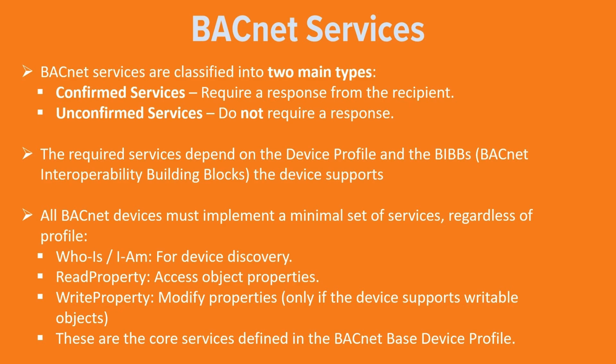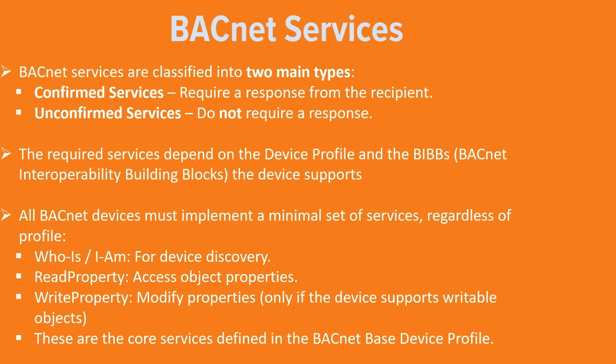Who-Is and I-Am for discovering devices on the network. Read Property to read object properties. Write Property to change properties, but only if the device allows writing. These are the core services in the BACnet Base Device Profile, the must-have stuff.